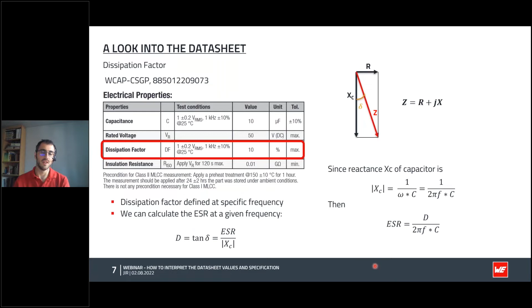Sometimes dissipation factor is used to calculate an estimation of ESR, but here it is even more important that we take into account the test frequency. When you convert dissipation factor to ESR, you have to use the frequency at which it was defined, so 1 kilohertz in this case. So this is the calculation of ESR. It is easy to calculate the ESR at this point, but only at this point, because the dissipation factor cannot be assumed to stay constant at other frequencies.